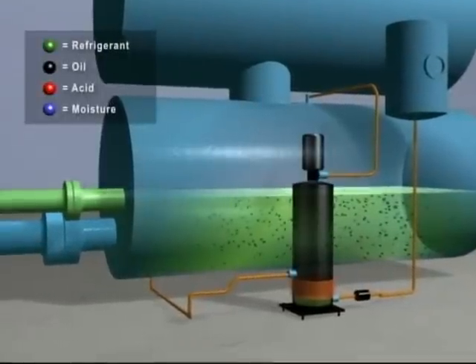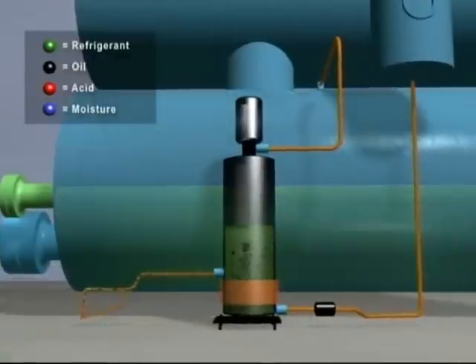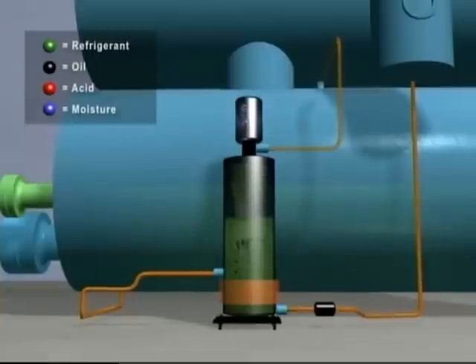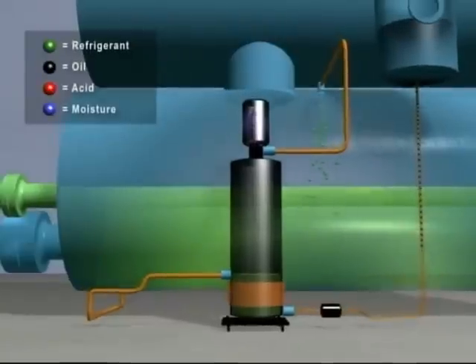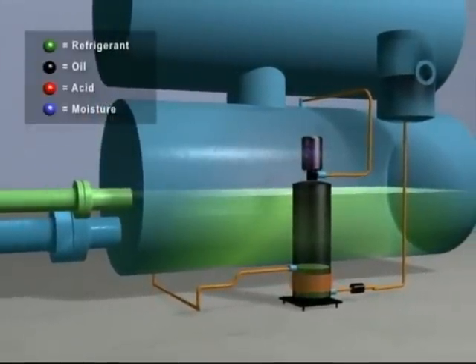Flow boiling results have been obtained for a newer enhanced boiling tube with R134A. The effects of oil on local and average boiling coefficients have been given. This enhanced tube shows a decrease in heat transfer with the addition of even a small amount of oil throughout various heat loadings. Even at 1% oil by weight, the heat transfer coefficient is reduced by 25% from its no oil baseline. At higher oil content, a 30% reduction has been typically measured.